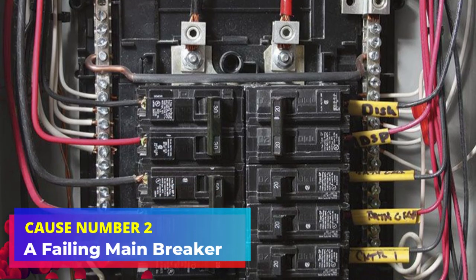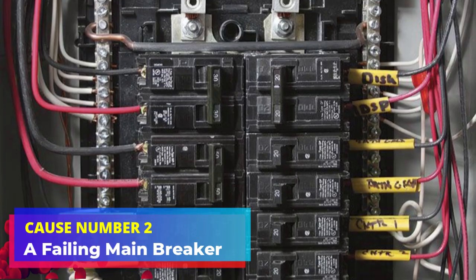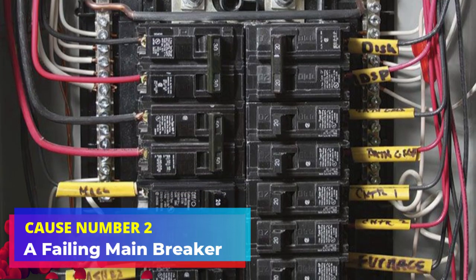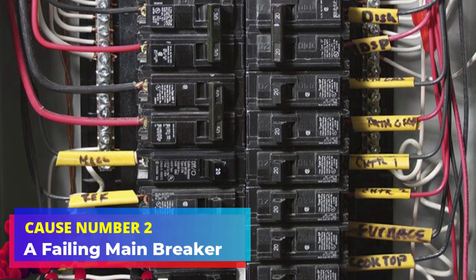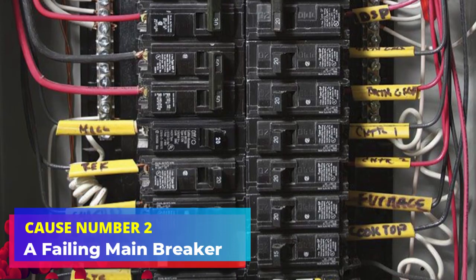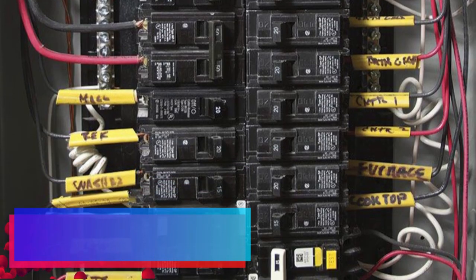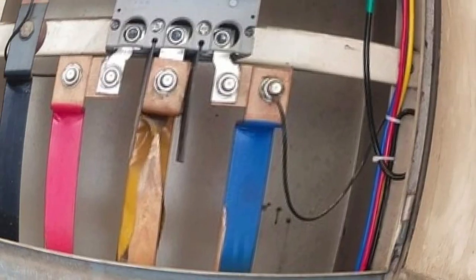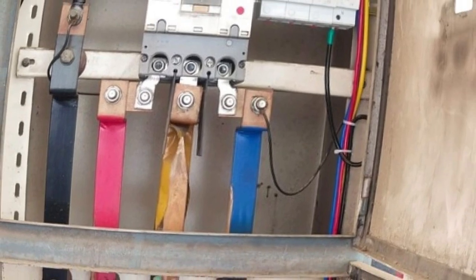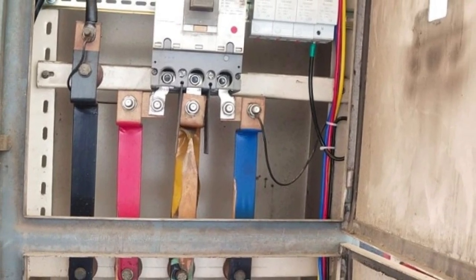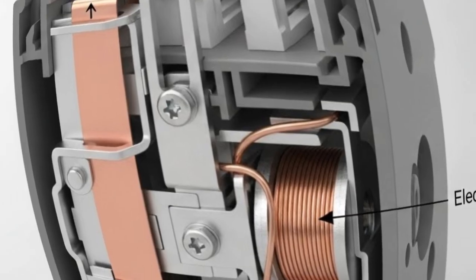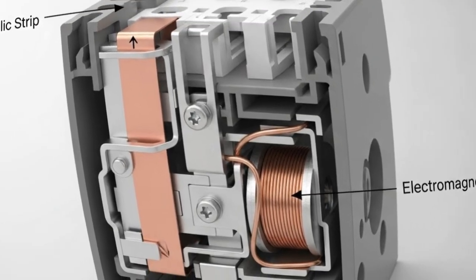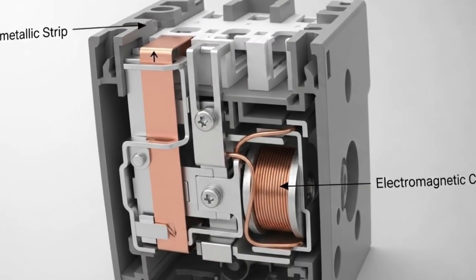Your main breaker is a mechanical device. Like all mechanical devices, it wears out over time. Inside the breaker, a bimetallic strip and an electromagnetic mechanism work together to detect overcurrent conditions. After years of use, these internal components degrade. The bimetallic strip can weaken. The trip mechanism can become overly sensitive. Contacts inside the breaker can pit and corrode.